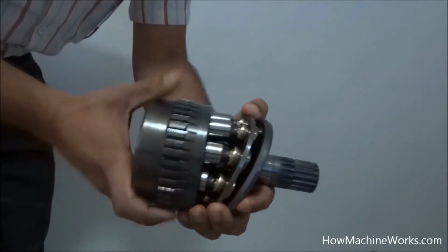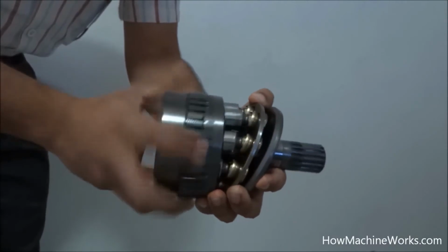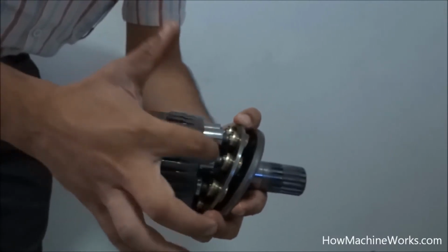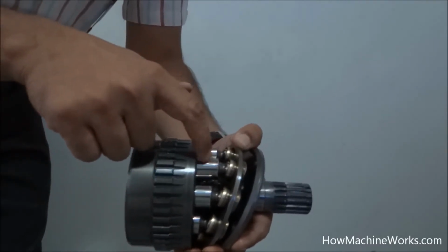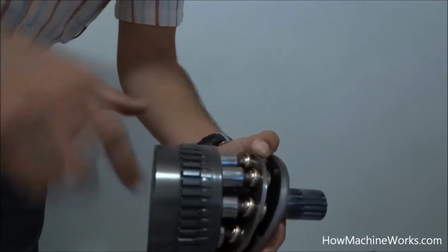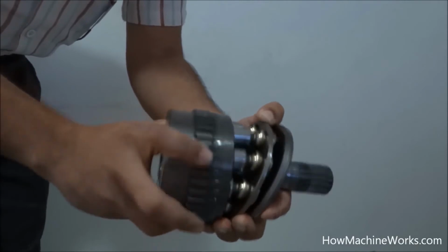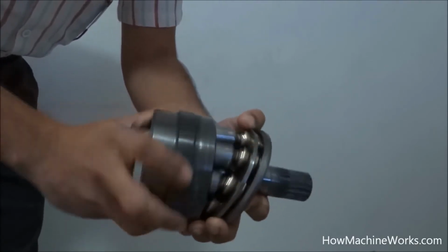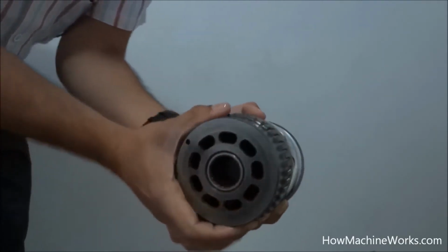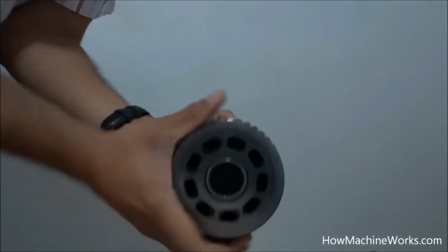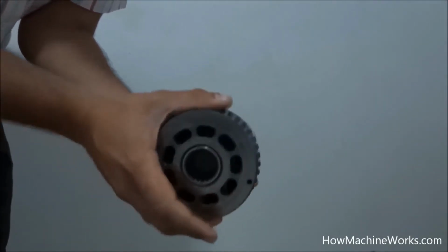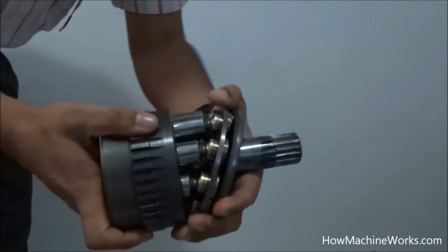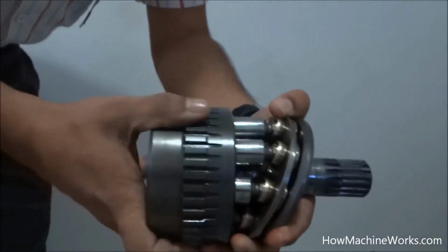So here you can see how the pistons actually move as the cylinder rotates. Both the drive shaft and the cylinder are rotating. At the bottom, the piston is moving back, which is creating a suction, and moving towards the top, the piston is actually reaching the maximum suction, and as it rotates to the other side downwards, the delivery is happening. You can see the piston movement inside the pots of the cylinder very clearly over there. Have a closer look, and that's how it exactly works.